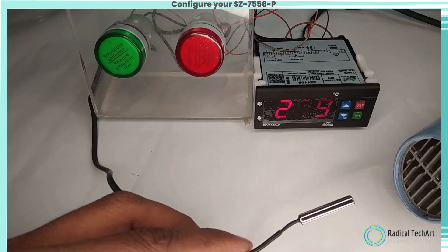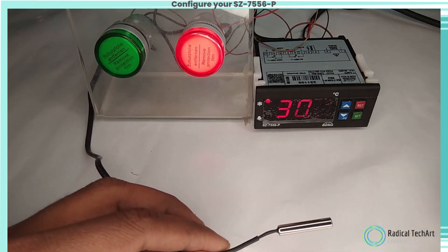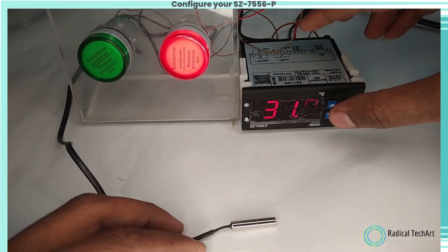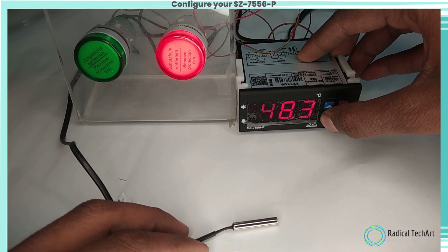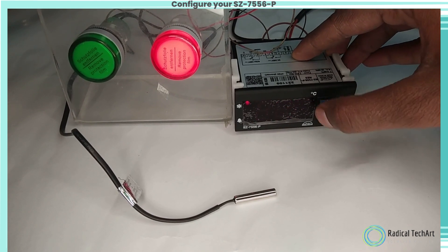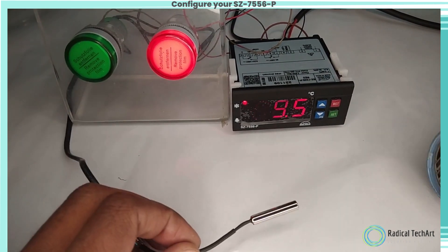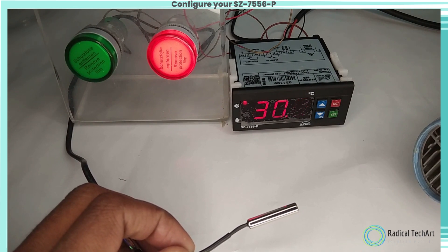Here is a demo of the SZ-7556-P Controller. We have set the set point to 25°C and are now heating the sensor up to 28°C. When the red light is on, the relay is on. After the temperature decreases from 28°C back to 25°C, it shows normal — the green light flashes. The LP parameter function is used to lock the keypad so that tampering is not possible by bystanders; 0 is for keypad unlocked and 1 is for keypad locked.